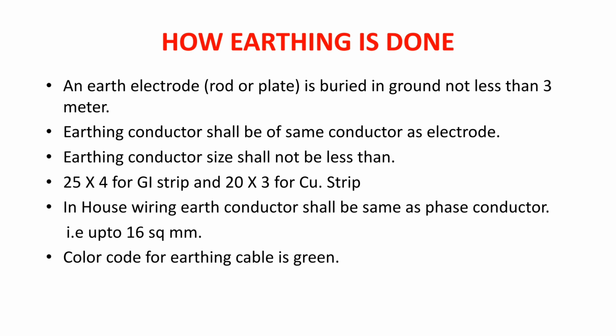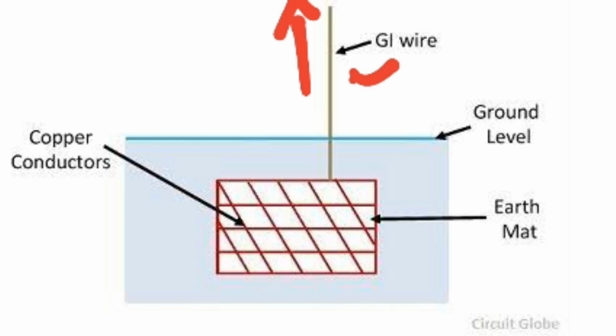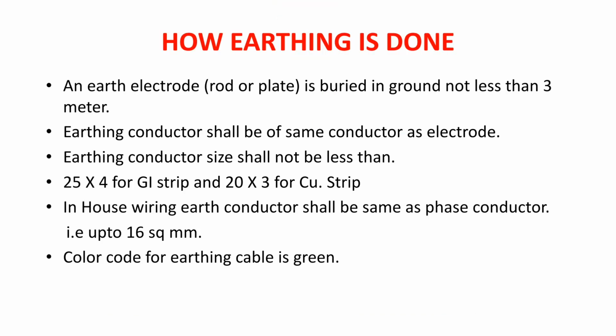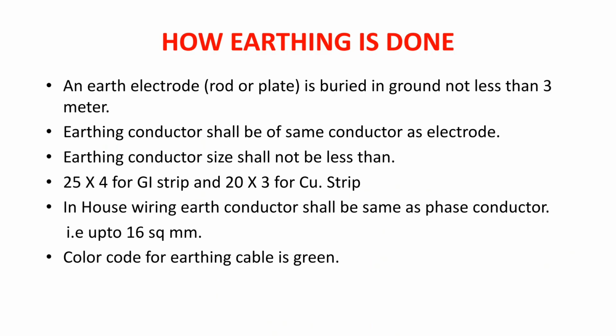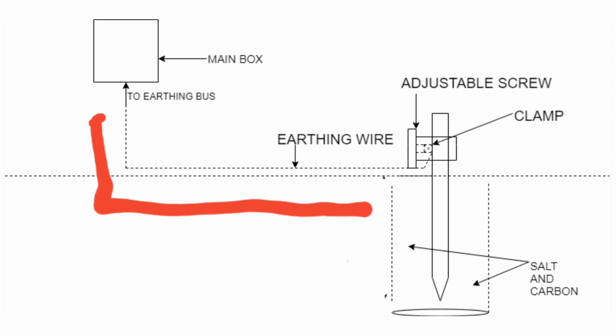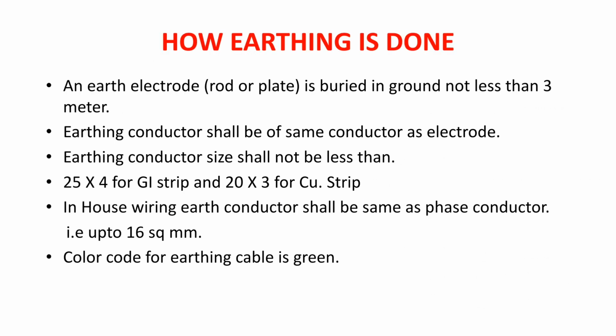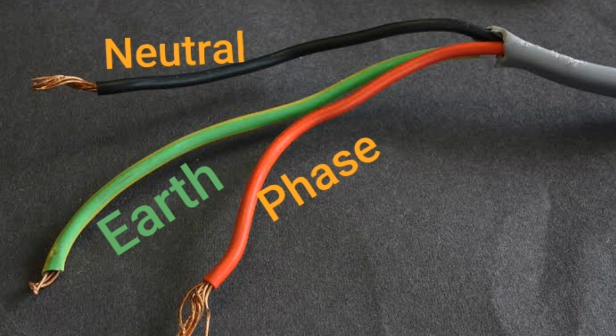Next we connect an electrical conductor to this electrode. This conductor can be a strip of GI or copper, or an electrical cable can be used, but this conductor should be of the same material as the electrode. Another question that comes to mind is what should be the size of this conductor? It should not be less than 25 by 4 square mm for GI strip and 20 by 3 mm for copper strip. This size is for main connections, and for sub wiring or house wiring we require the same conductor as our phase conductor, up to 16 square mm. These sizes are for house wiring, for low load connections. For higher connections it will be different. Friends, the color coding of earthing cable is green, and the symbol of earth is this.